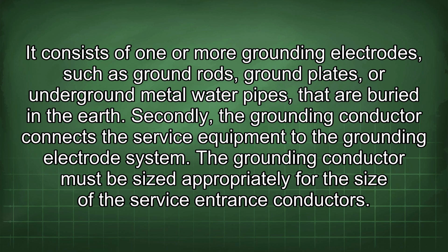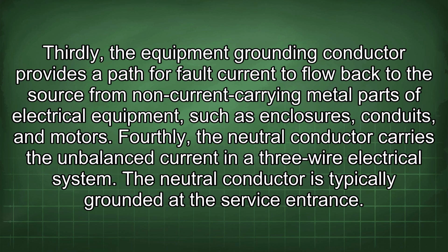Secondly, the grounding conductor connects the service equipment to the grounding electrode system. The grounding conductor must be sized appropriately for the size of the service entrance conductors. Thirdly, the equipment grounding conductor provides a path for fault current to flow back to the source from non-current carrying metal parts of electrical equipment, such as enclosures, conduits, and motors. Fourthly, the neutral conductor carries the unbalanced current in a three-wire electrical system. The neutral conductor is typically grounded at the service entrance.